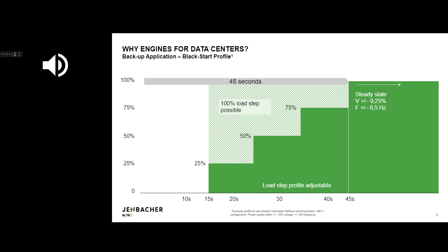Just an important note here, because yes, many technologies claim this fast start, but it's very important to know the difference between fast start capability and transient performance. Fast start is basically the capability of starting a unit fast and applying load quickly, which is obviously a benefit. But much more important than fast start capability is also the capacity of accepting load for this unit.